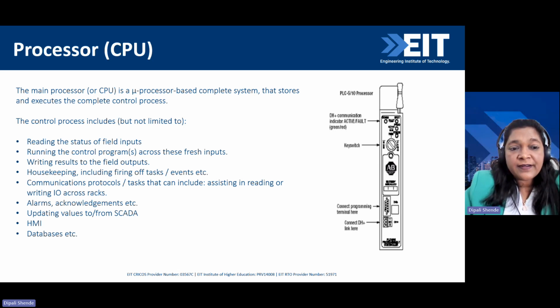It will read the status of the field inputs, then run the control program across these fresh inputs - running means it will execute the program - writing results to the field outputs. Then housekeeping, including firing off tasks, events, etc, and communication protocols.